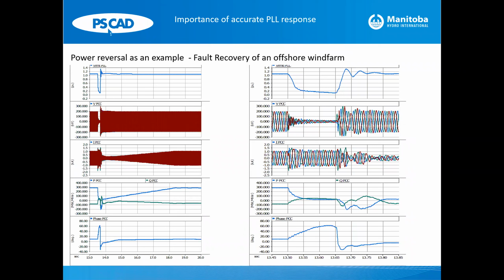This was quite difficult to explain to clients previously, but the core reason behind this is that the PLL angle was not measured correctly. Let's say the angle was really 30 degrees in real life, in actual measurements, but the PLL was estimating it to be, for example, say 60. This results in the power to reverse, okay? This power reversal would result in DC voltage to rise, okay? And in this case, if you have a DC chopper, and as long as it's sized correctly, then it would ride through the fault. However, if you don't have it, then the wind farm can trip. So the utilities typically don't like power reversals, and generally ask manufacturers to retune or redesign their converters to avoid this, which in many instances is very challenging.